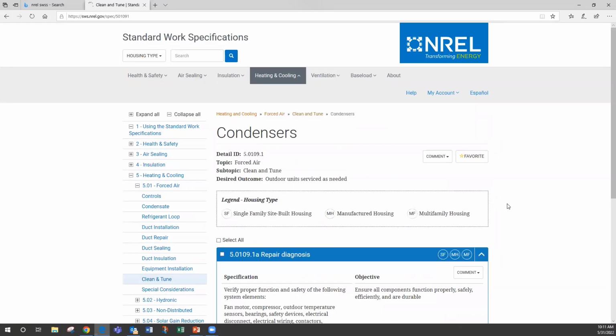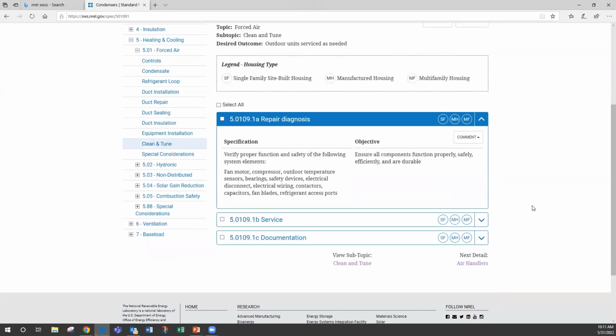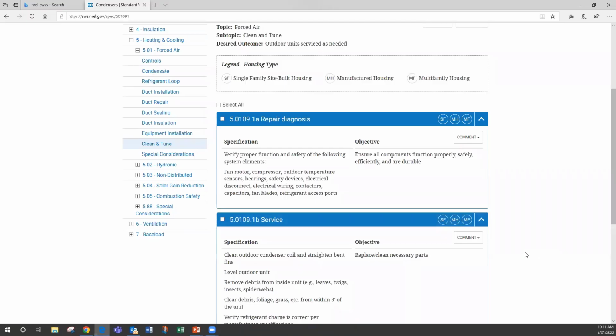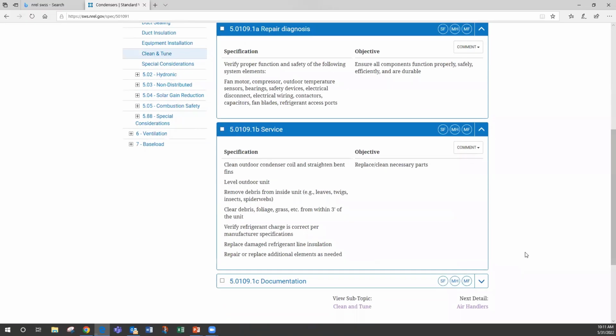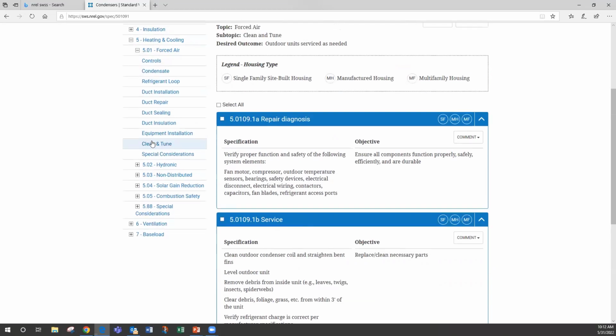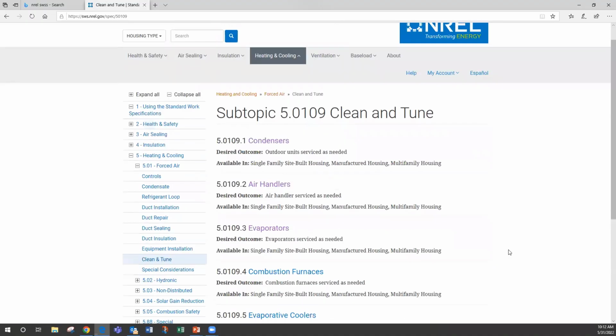So clean and tune for the condensers. This is the outdoor unit. Verify proper function and safety: fan motor, compressor, outdoor temperature sensors, bearings, safety devices, electrical disconnects, capacitors, contactors, all the stuff that we should be doing as a quality clean and tune. Clean the outdoor condenser coil, straighten bent fins, level the unit, remove debris, and verify refrigerant charge is correct per manufacturer specifications. Replacing damaged refrigerant line insulation should be part of that. So again, this is where we go for guidance on the desired outcomes.